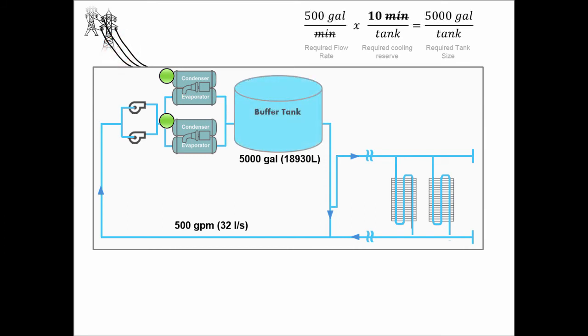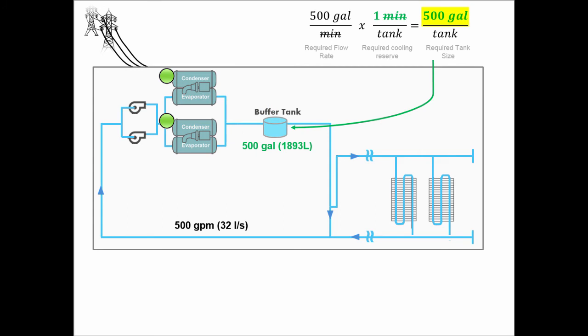So in our example, if a chiller with quick start was implemented, and we reduced the chiller restart time to approximately one minute for a nice round number, then the customer could reduce their buffer tank size to only 500 gallons, or one-tenth the original size, which translates to money and space savings that can be re-appropriated toward the data center's purpose.